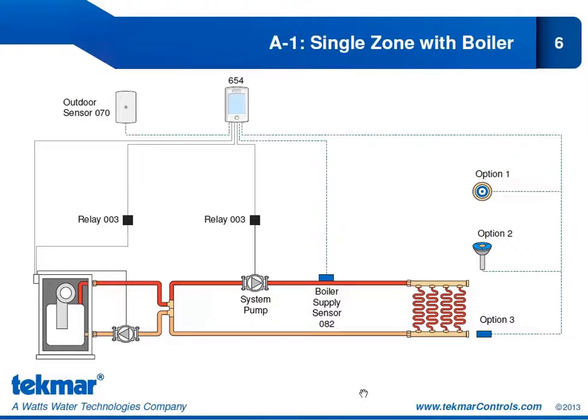So you can see on the right-hand side, we are showing 3 sensor options. Option 1, which is a 090 or 094 snow ice sensor, and that, of course, gives us the automatic start and stop. Option 2 is our 095 snow sensor. So this is our aerial sensor. And of course, as we learned in the previous training block, this sensor does not measure the slab temperature. So we recommend combining option 2 with option 3. Option 3 being your slab sensor 072 or 073.